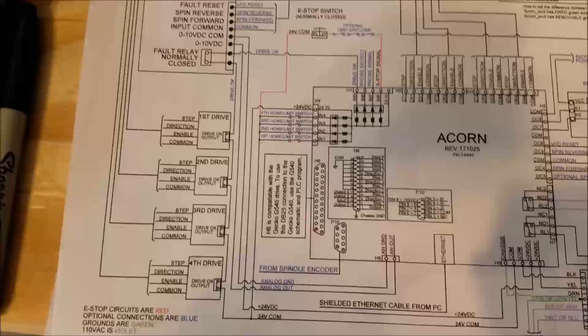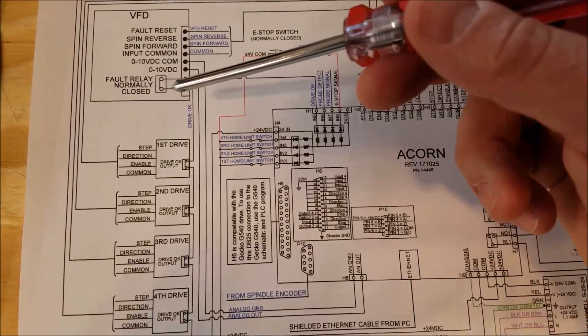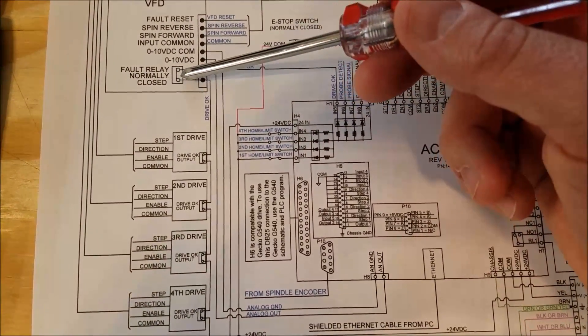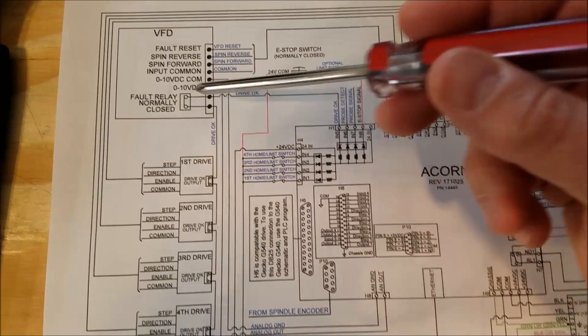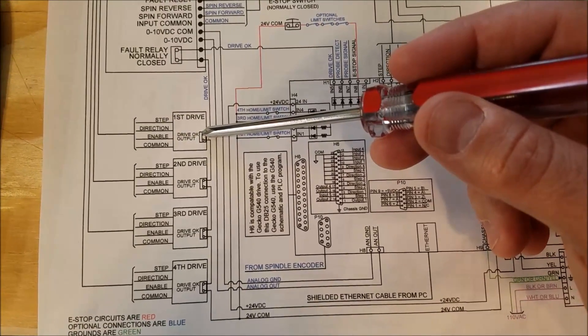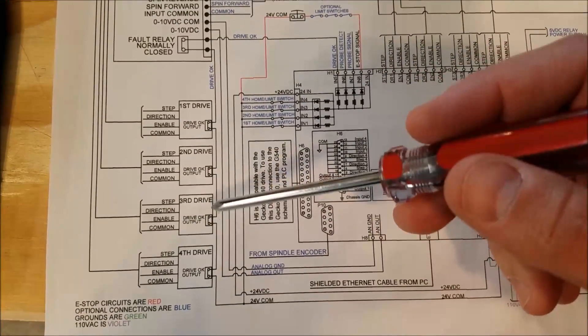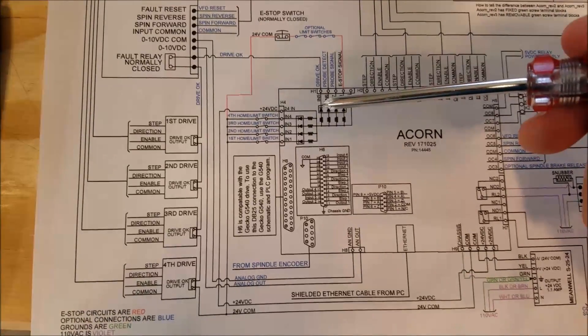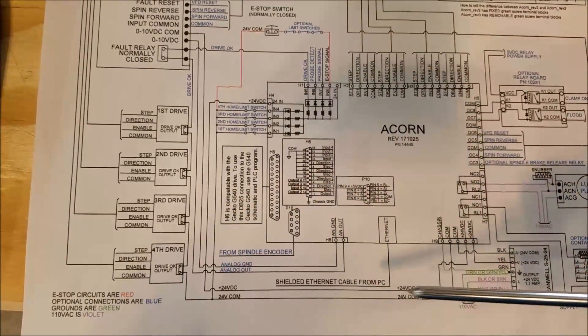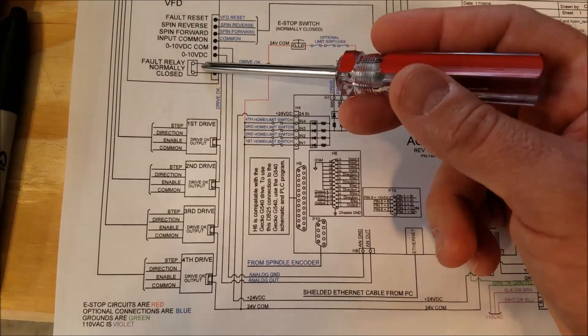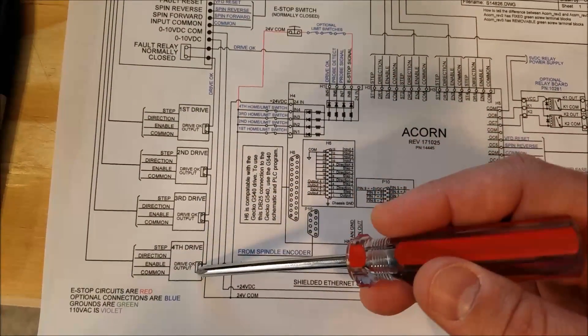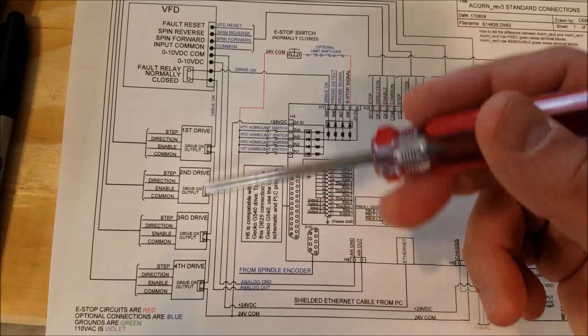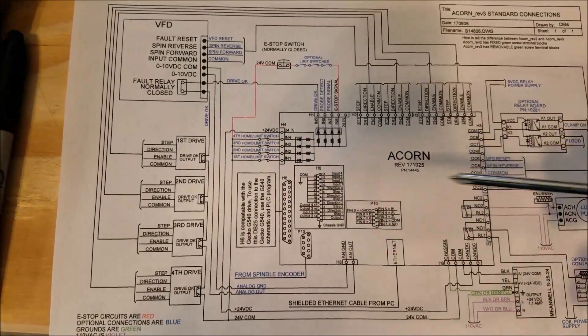So you wire up this big loop and make all of these circuits normally closed. When the VFD is happy, it's closed. When drive number one is happy, it's closed, and so on. So when everything is good, this circuit's closed and the Acorn will run.